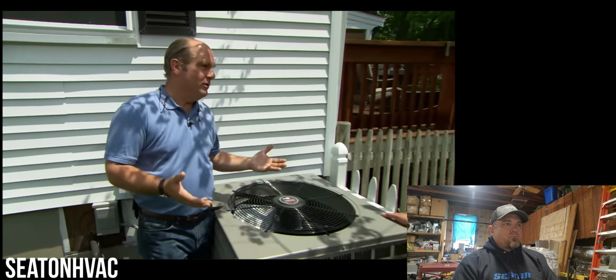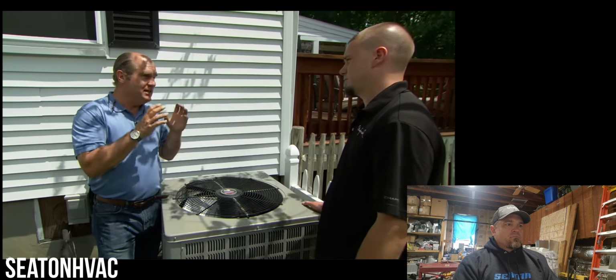Now it goes back a long time. There was a time in this country when the way we conditioned a building or stored food safely was with ice. You guys ever seen those old videos where the big Clydesdale horses are pulling those big ice blocks? This is what he's talking about here. Every local town would have an ice house that stored ice all through the year. And it was a measure of how much cooling power you could get out of 2,000 pounds, a ton of ice. Now the modern refrigeration industry borrowed that term. And nowadays we think in terms of 12,000 BTUs as a ton of cooling.